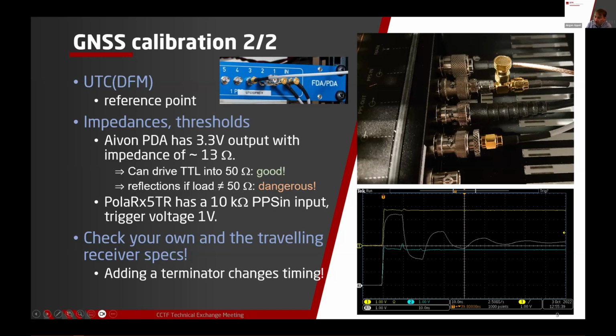So on our GPS receiver, the input impedance is high impedance, so it's a really good idea to put a terminator there. If you don't do that, you get reflection signals, as you can see here on the bottom, and the traveling receiver didn't have that. So you have to be careful that you don't trigger on the wrong edge. Just always be aware of what you put in and monitor with an oscilloscope, and be sure what you're doing. Don't follow blindly what's in the manuals.